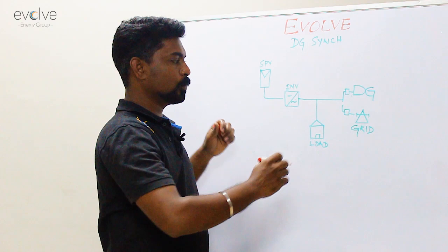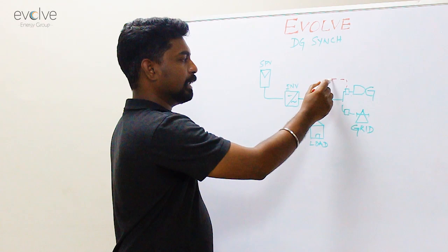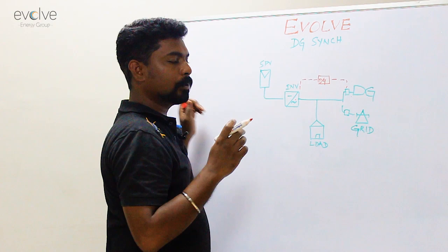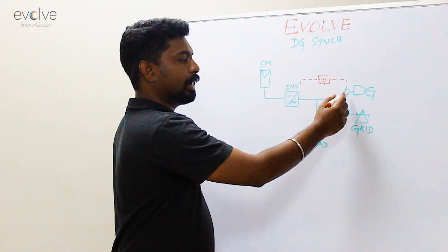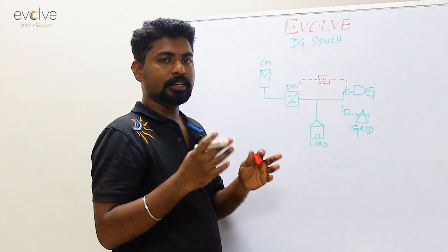There are three parts involved in a DG sync. One is a bi-directional energy meter. Second is the actual DG sync device. And then the inverter itself. You will have to tell the inverter when to start and how much to generate, ensuring the DG is always given its 30% load. This bi-directional energy meter senses the output of the DG, and when the DG reaches its 30%, it gives a signal to the inverter to start. When the inverter starts generating, the DG need not run for excess load because the solar is taking over the excess load.